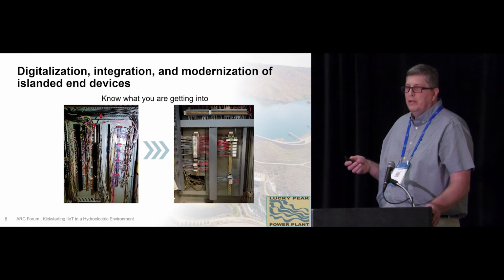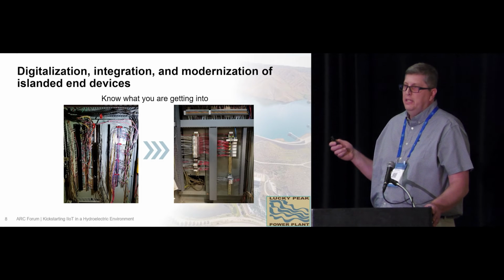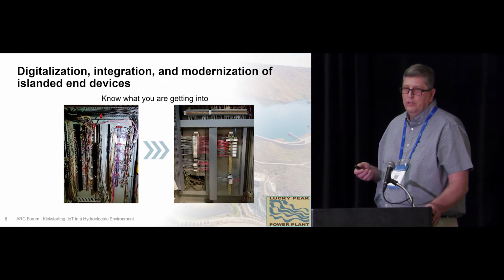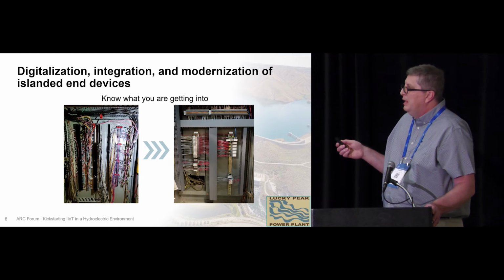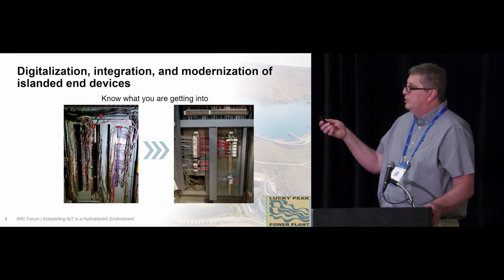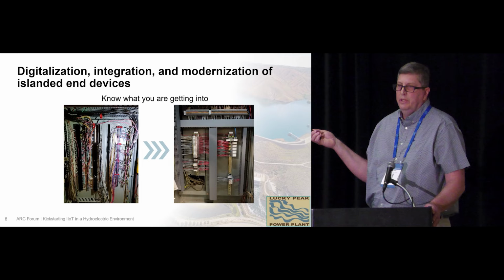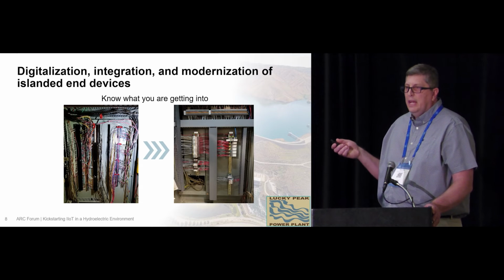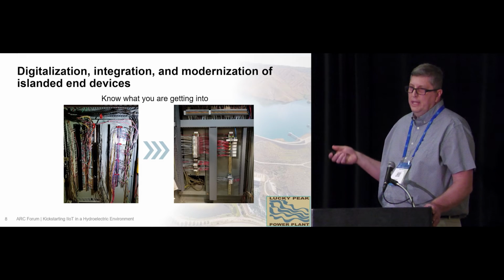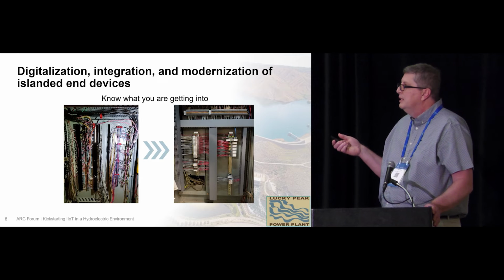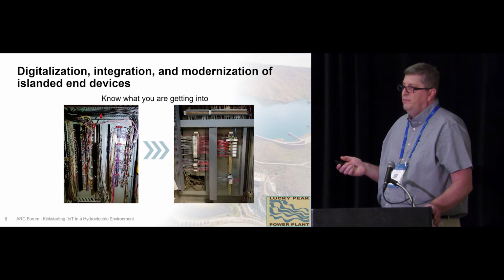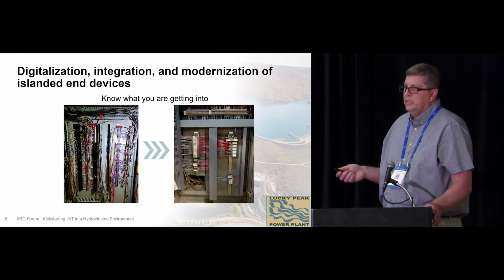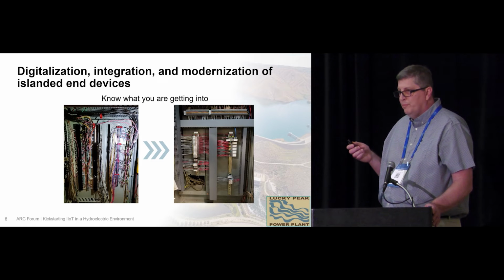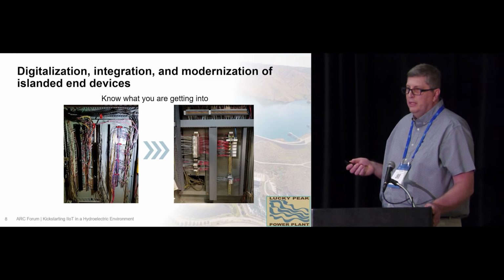So part of the task before we even started getting to the end devices is we knew we needed to do some housekeeping. Pretty much everything on the left fit into one terminal strip at the very top of the screen on the right. That allowed room for all the relays, all the I/O, and a couple other things. By going through those circuits, we were able to relabel, redocument, and that process cleaned up a lot of things for us.